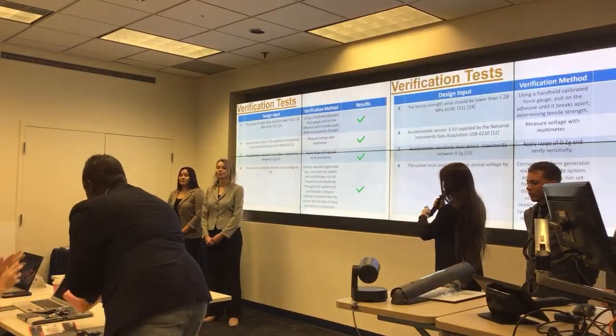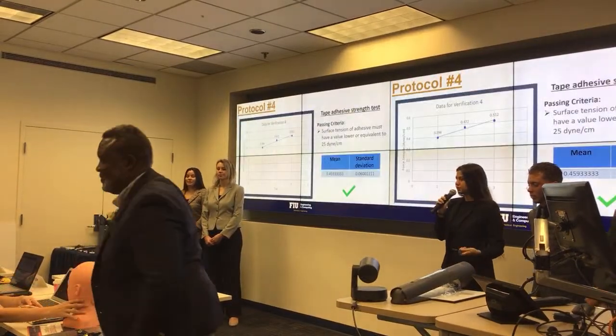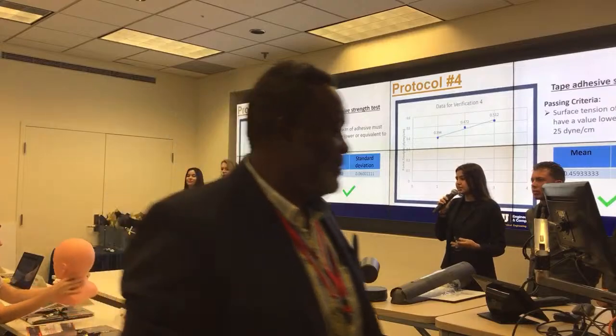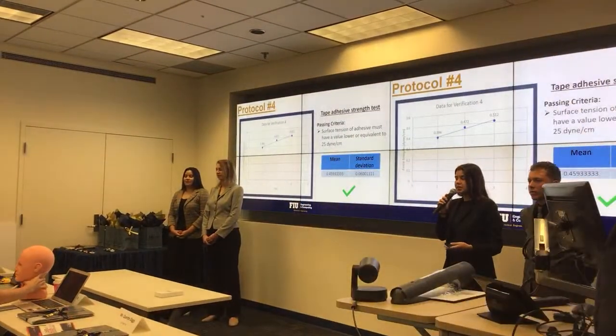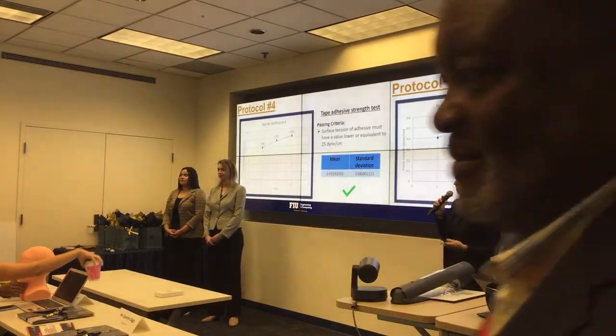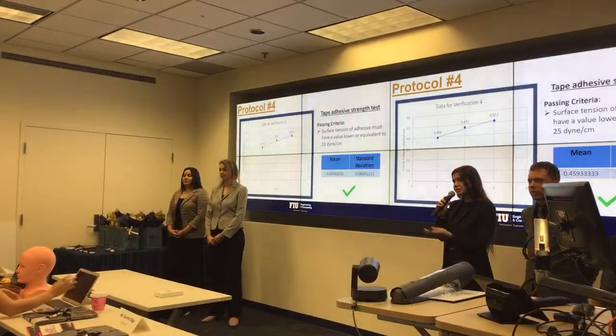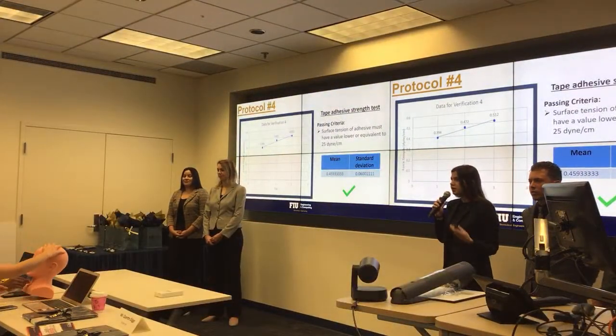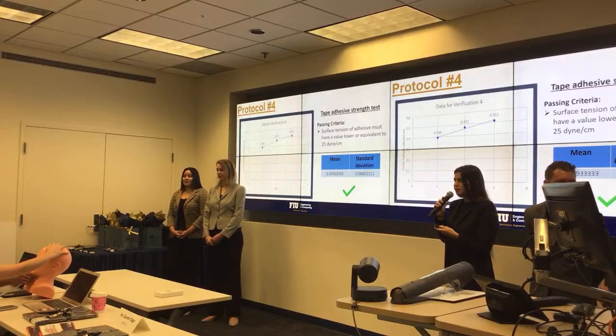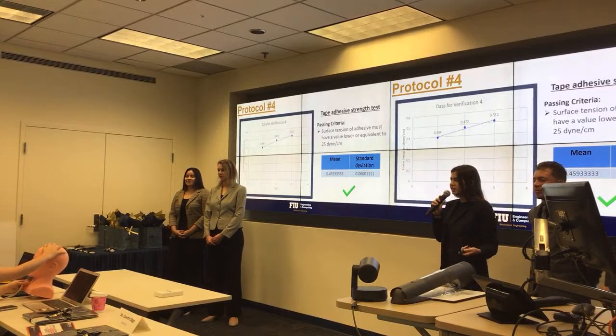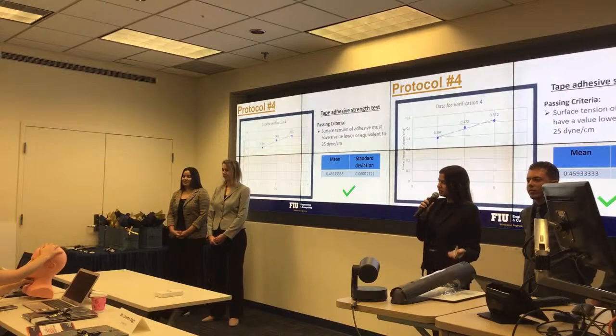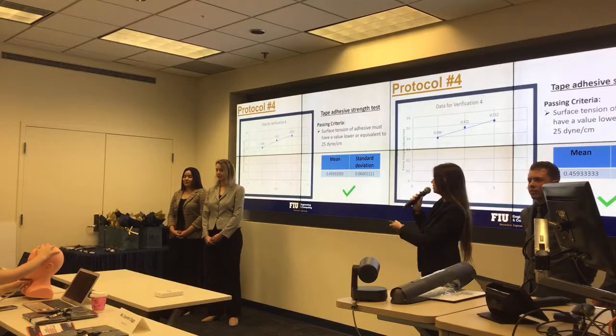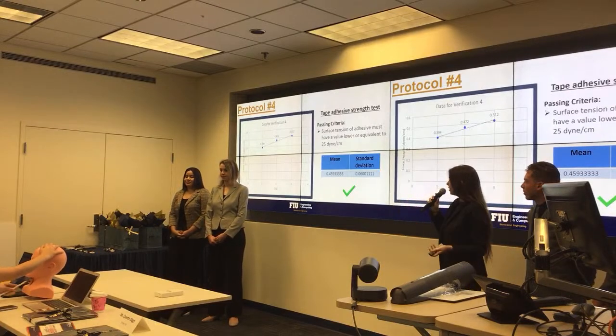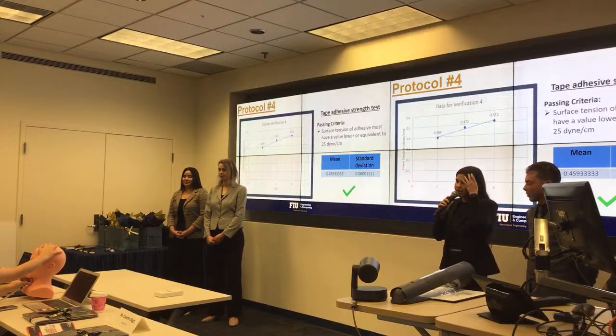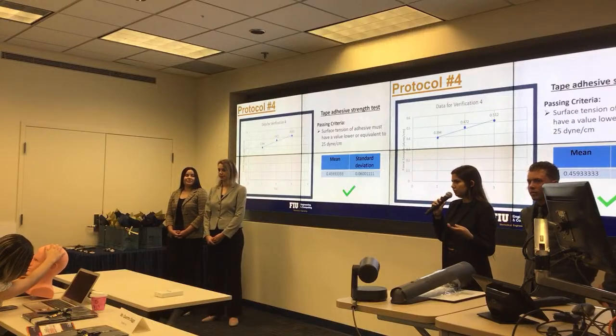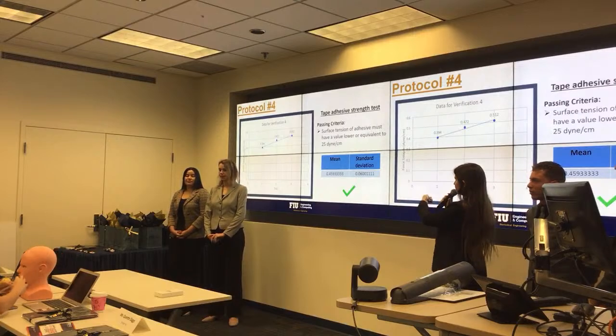Now moving on to protocol number 4, which details the strength of the tape's adhesiveness. Due to the skin being a low surface energy substance with a surface tension between 25 to 29 dynes per centimeter, we concluded that our tape chosen must have a lower or equivalent surface tension in order to ensure both patient comfortability and device reliability. So as seen in the table and graph, all of our findings meet these needs, and this protocol was also successful.